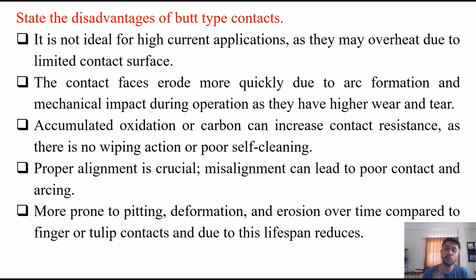The contact faces erode more quickly due to arc formation and mechanical impact during operation, as they have higher wear and tear. Accumulated oxidation or carbon can increase contact resistance as there is no wiping action or self-cleaning action. Proper alignment is crucial. Misalignment can lead to poor contact or arcing. They are more prone to pitting, deformation and erosion over time compared to finger or tulip type contacts, and due to this, the lifespan of these contacts is reduced or limited. So these are several disadvantages of butt type contacts of circuit breaker.